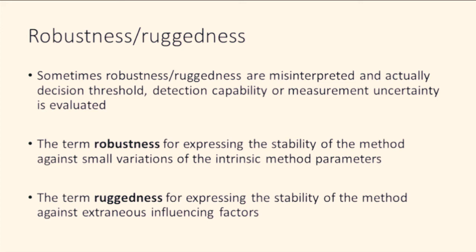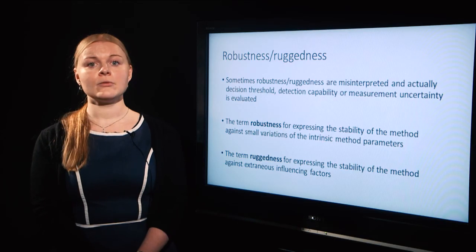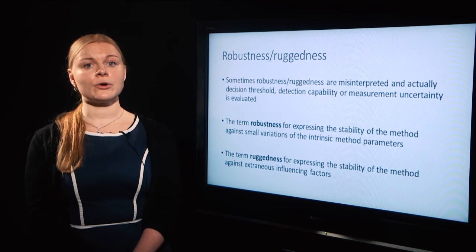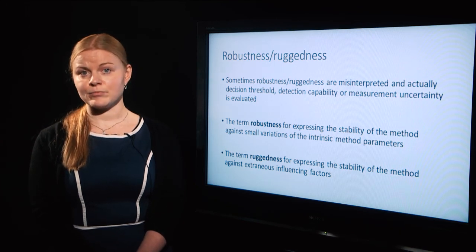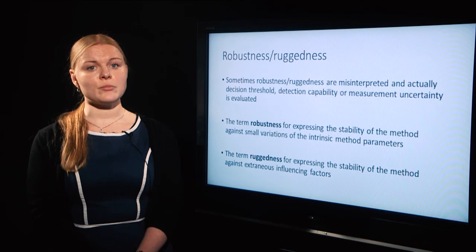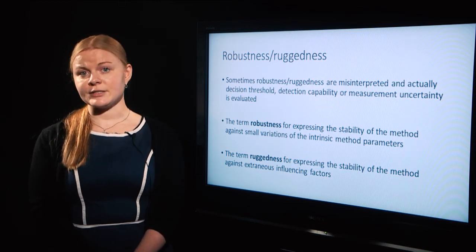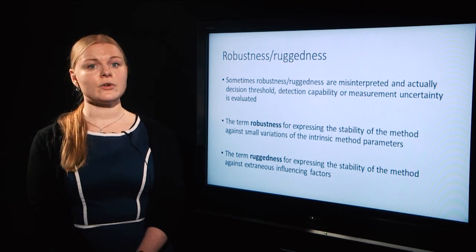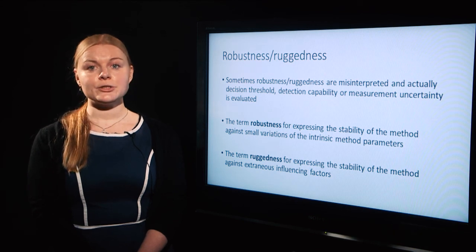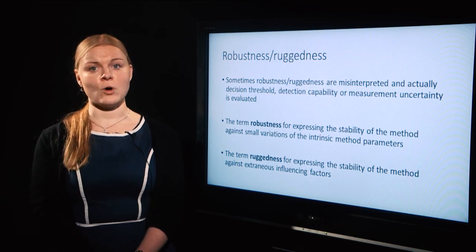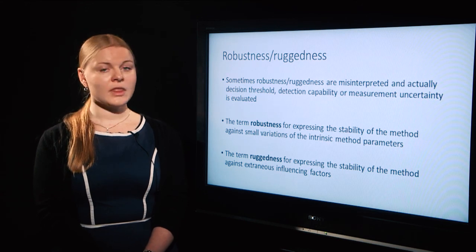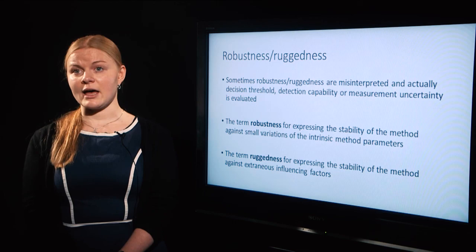In this course we use the term robustness for expressing the stability of a method against small variations of the intrinsic method parameters, and the term ruggedness for expressing the stability of a method against extraneous influencing factors. We address changes of the method parameters meaning within-laboratory assessment of robustness and variability of a sample matrix. We do not explicitly address the changes occurring when a method is transferred from one laboratory to another. This was the short introduction to robustness and ruggedness.